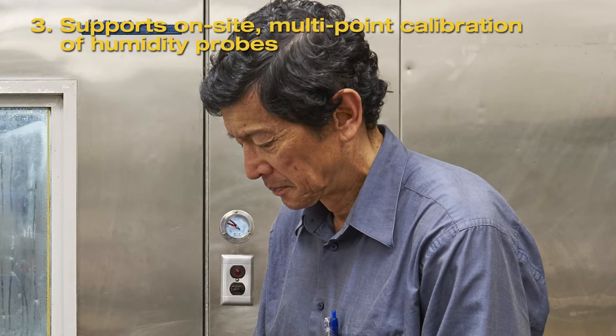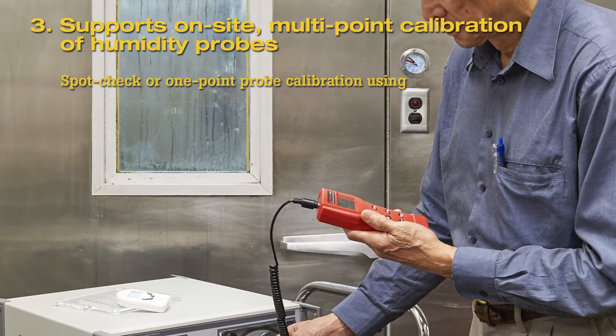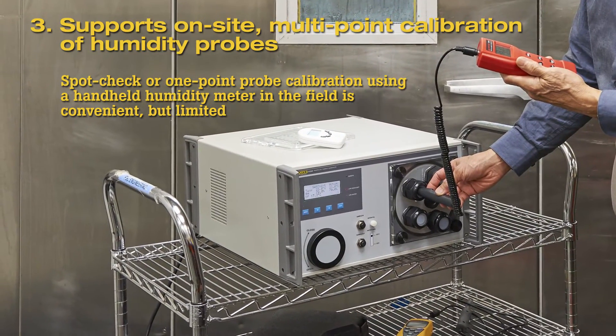Third, support for on-site multi-point calibration of humidity probes. Spot check, or one-point probe calibration using a handheld humidity meter in the field is convenient, but limited in value. When calibrating with a handheld meter, external influences can cause humidity measurement errors, and one-point tests may cause out-of-tolerance readings when ambient conditions change. Using the 5128A RHapid-Cal to calibrate over multiple humidity and temperature points gives a more reliable test and truer characterization of how a humidity probe actually operates over its working range in the field.